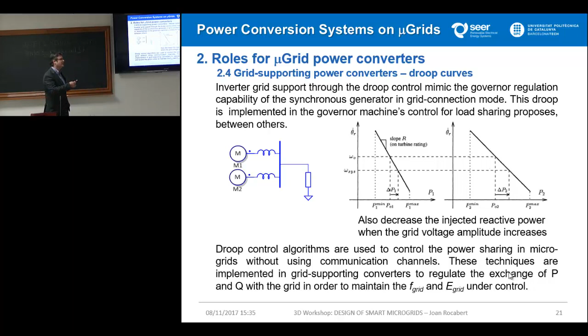Usually we get, as we read, a relationship between the active power and the frequency, and also between the reactive power and the voltage level of the microgrid. But this is because usually, not always, the microgrid behaves as an inductive line. What happens in the low voltage grid? In the low voltage grid, the line is more resistive, and we can reach levels where the line is so resistive that we get the crossing effect. So if we inject more or less power, what we are modifying is not the frequency but the voltage of the microgrid. And in the extreme, if we inject or absorb more or less reactive power, what we are modifying is the frequency of the microgrid.